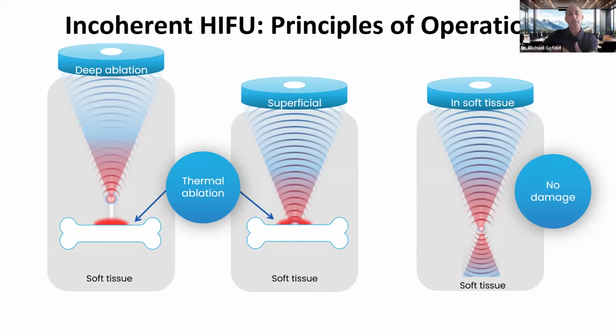So that gives us an opportunity to put the center of the lesion a bit above the bone or beyond the bone. It will create the lesion regardless, as long as the focal zone is within 5 centimeters. Now, what if there's no bone? As you can see here, there will be no damage because the beam will meet, cross, and dissipate. That's why in incoherent mode, there will be no thermal lesion of the soft tissue.